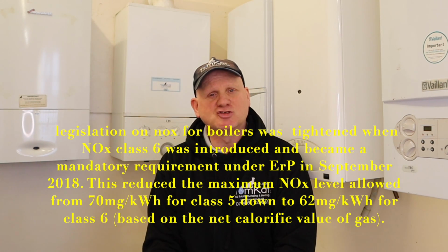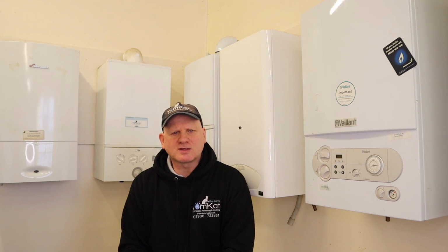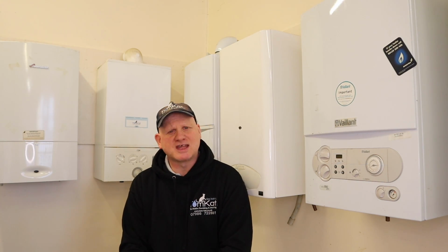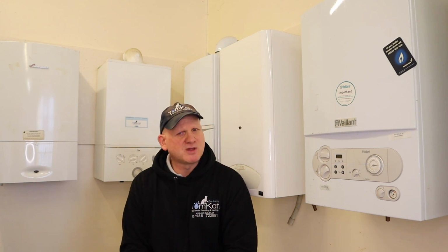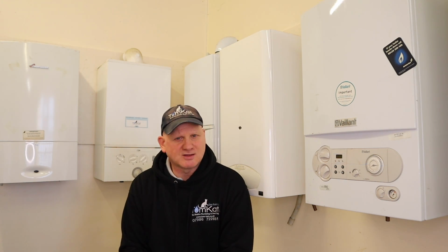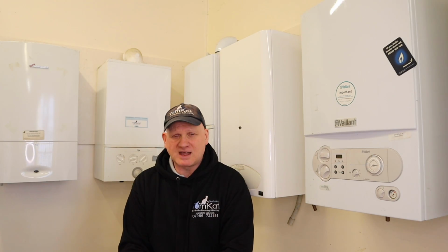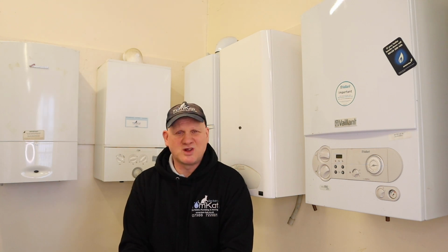It can be crucial to look at the nitrogen oxide levels produced by the boiler when you're working in inner city areas. How is this boiler going to be looked after? Is it going to have a planned maintenance scheme with it? Is it going to be checked every year? Because most domestic properties don't have their boiler serviced. What are the warranties for the heat exchanger and the boiler, and who's going to control the pH levels? And finally, the cost factor. Most domestic customers don't really care whether they're using a stainless steel or aluminium heat exchanger. They just care about how much it is going to cost.